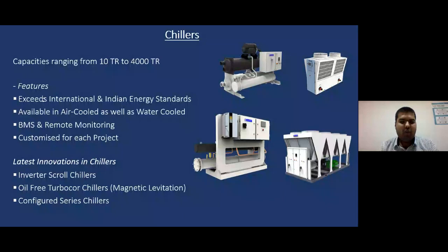The latest innovations in chillers are inverter scroll chillers, basically with inverter compressors. There are oil-free Turbocor chillers. Oil-free Turbocor chiller means the compressor would have no oil in it, and it would work only through magnetic levitation. The starting current of this chiller is only 2 amperes. So you can imagine the power consumption which we could save with oil-free Turbocor chillers. And the configured series chillers are basically the customized chillers which the company can make.